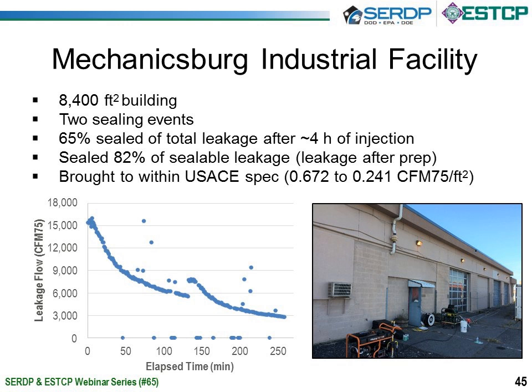Okay, so now I'm going to talk about a couple of the demonstrations that we performed. This demonstration was in Mechanicsburg. It was an industrial facility. It was an 8,400 square foot industrial site used for training. It took 2 sealing events to seal this building, and overall, we were able to seal 65% of the total leakage in the building in about 4 hours of total injection time. We actually sealed 82% of the available leakage, so that's the leakage after we prepped the building.